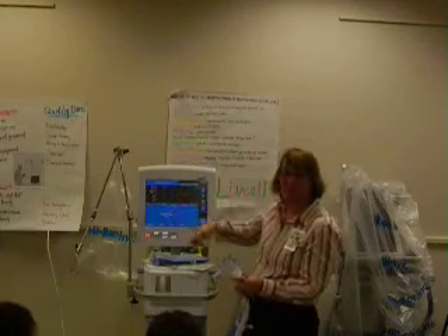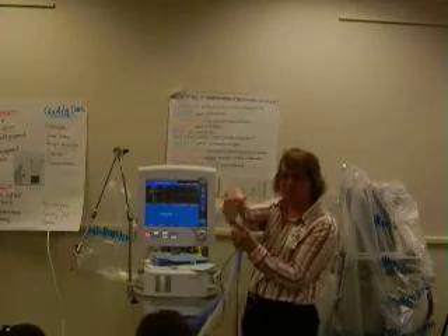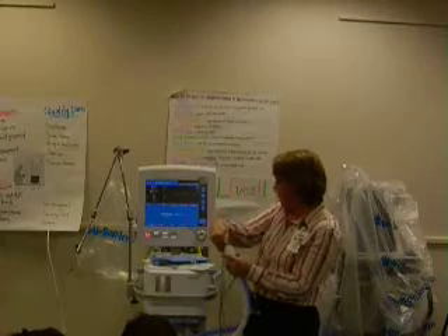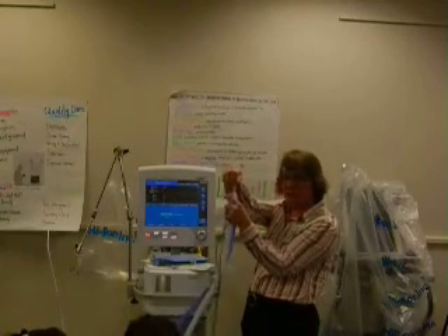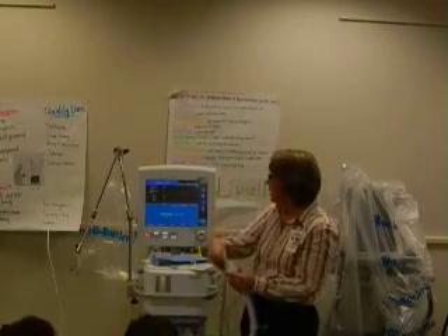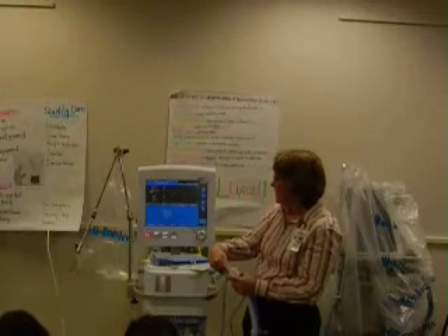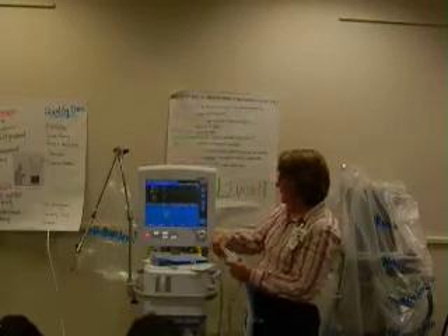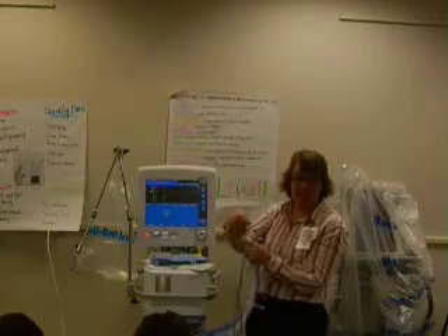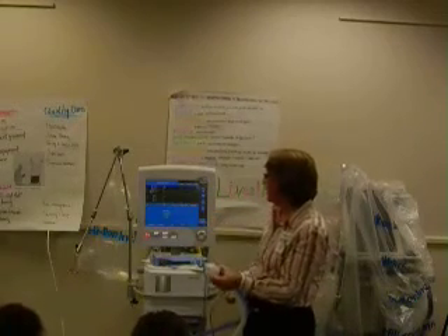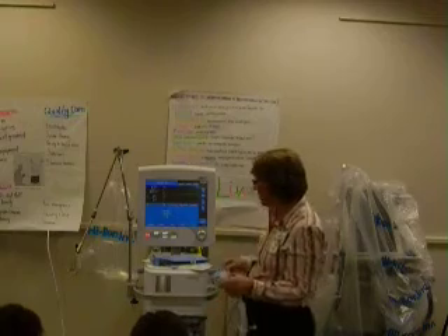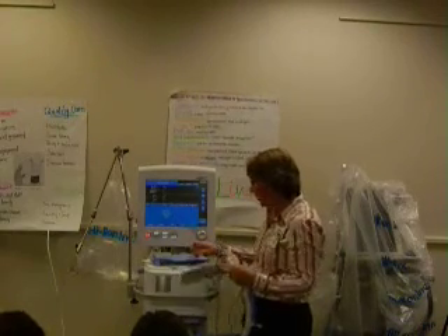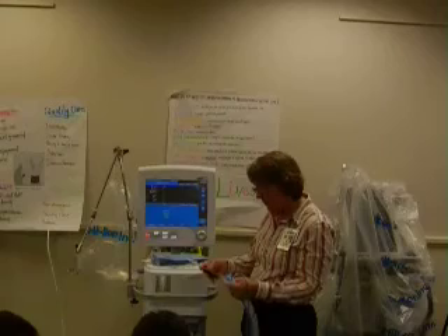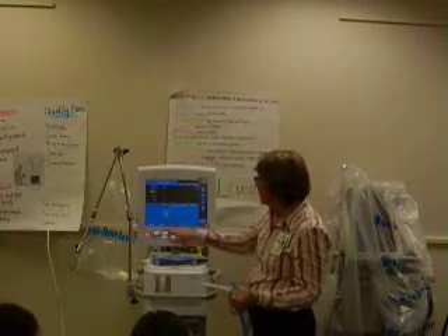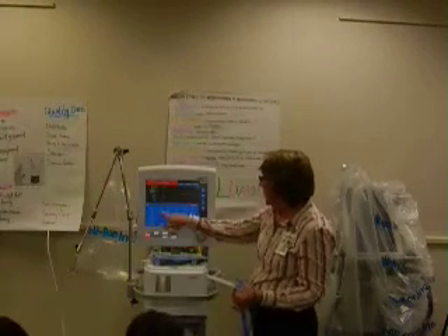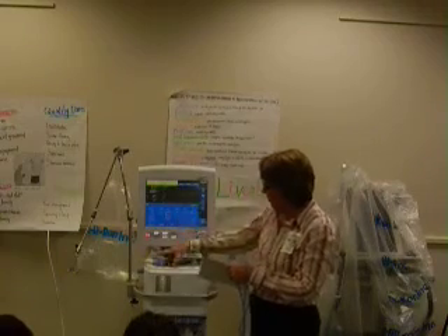Tighten patient system. What it wants you to do is cover it, tighten it, through this. It's testing for leaks. It's just making sure our circuit's secure. It says patient system tight now. And see, now we're just getting high pressures. It's done. Once you see patient system tight, you know you're good. That's tested all the circuit for leaks. Now it says press monitoring window. So we're going to go there. And we have to hook our lung back up.